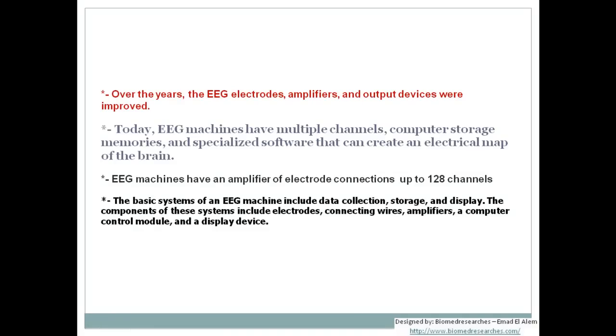Over the years, EEG electrodes, amplifiers, and output devices have been improved. Today's EEG machines have multiple channels, computer storage, and specialized software that can create an electrical map of the brain. Amplifiers can support up to 128 electrode connections, though routine EEG typically uses around 21 electrode channels. Modern amplifiers can have 32, 44, 64, or up to 128 channels, used for research and special cases.